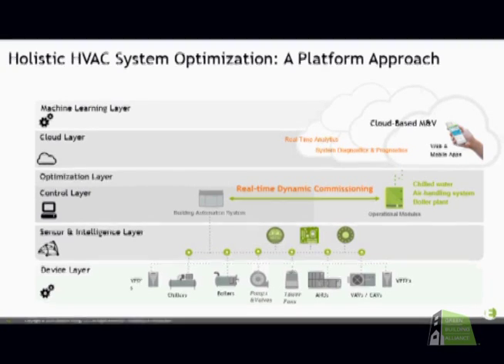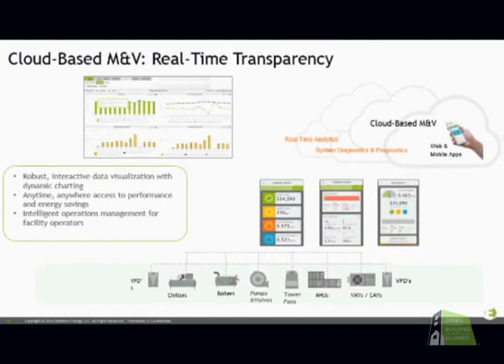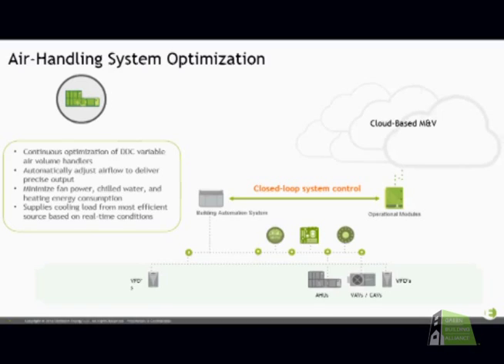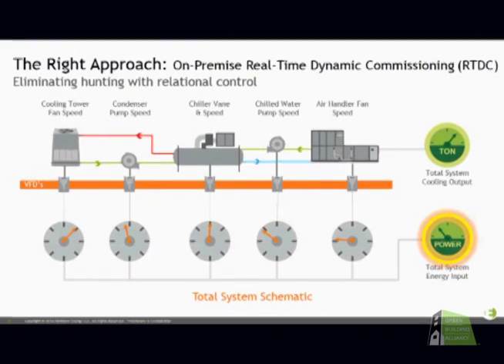Well, just to get a little more in depth on one point you mentioned, about a plate and frame heat exchanger - for those not as familiar, what that's used for in this sort of plant is what we call free cooling. So instead of a chiller sequenced in, let me see if I can go back to that - where you have the chiller in this particular illustration, you just have a heat exchanger.